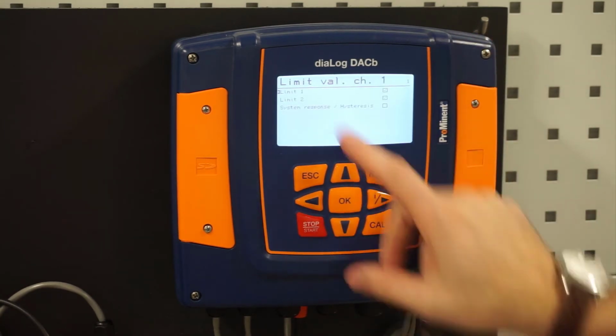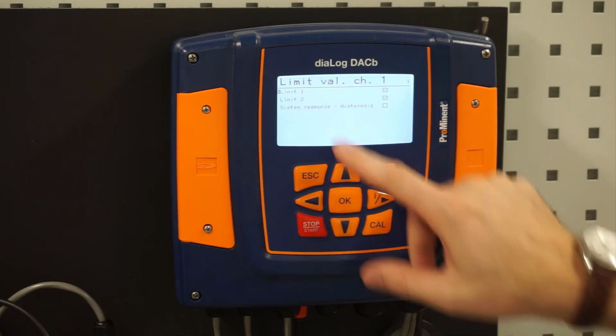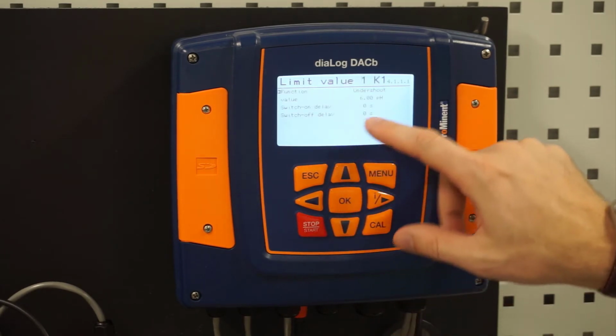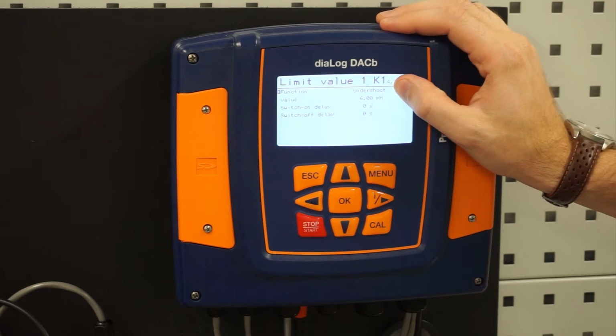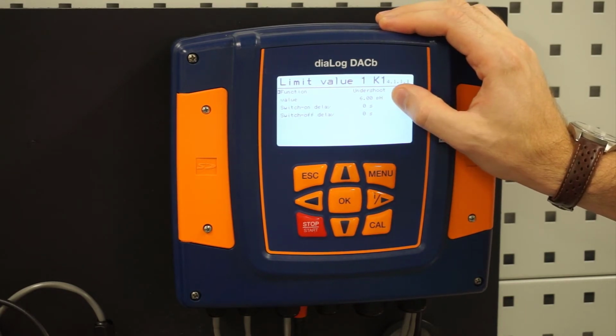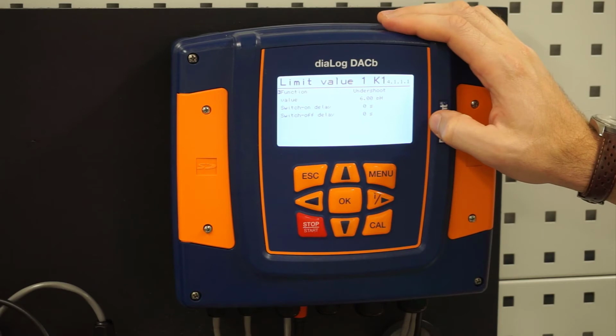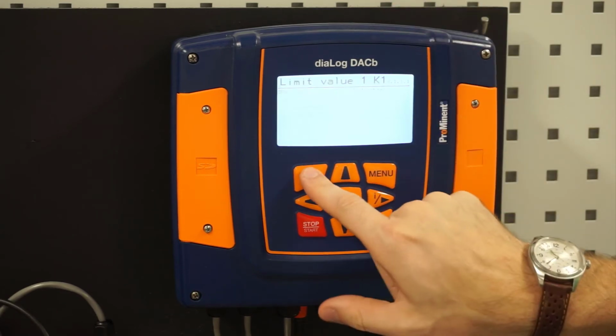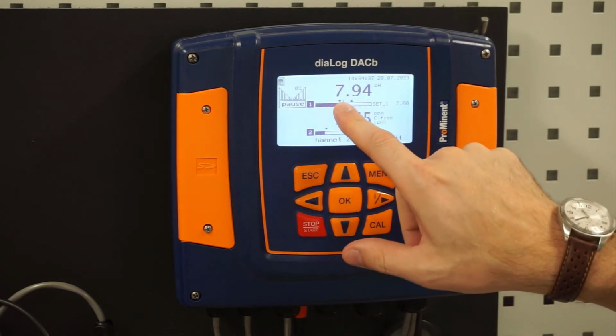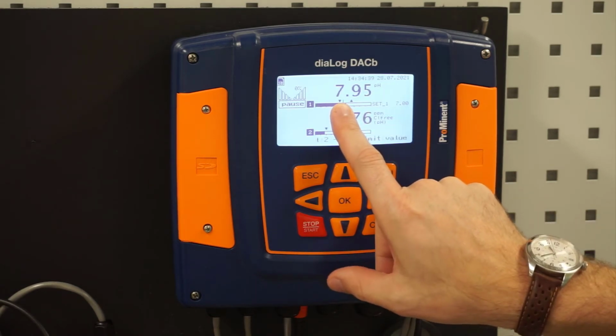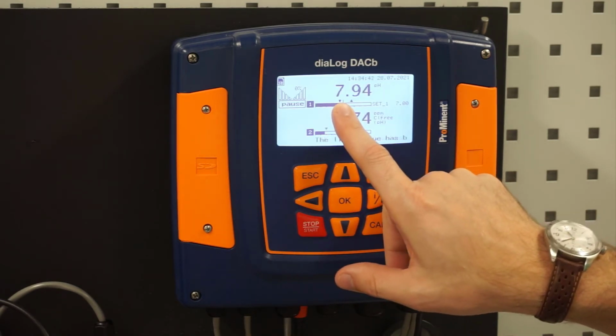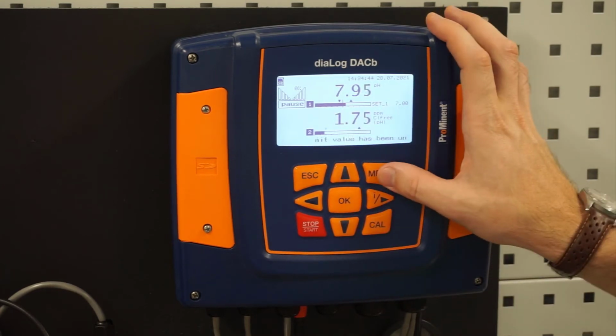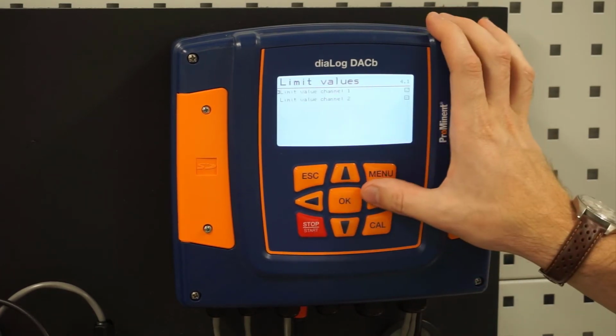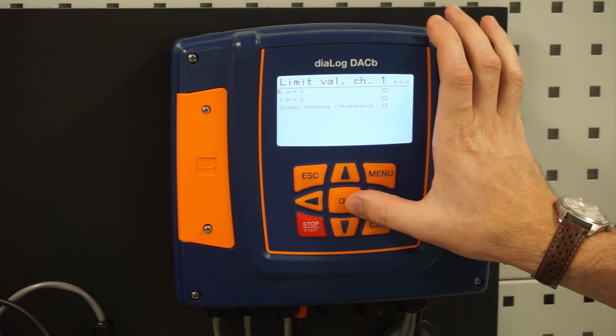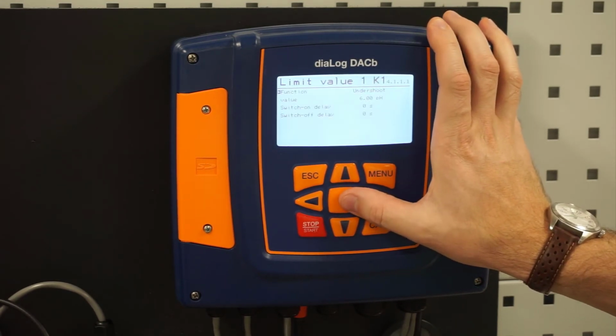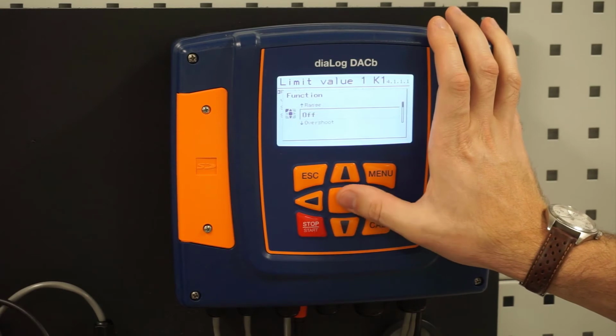I have 2 limits in channel 1. My first one is my undershoot limit. Right now it's set at a value of 6. If I back all the way out, that is what this down arrow represents: my lower limit of a pH of 6. If I don't want that on, I simply go to the function and turn it off.